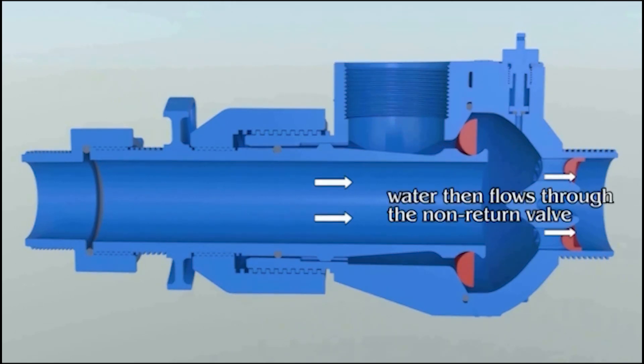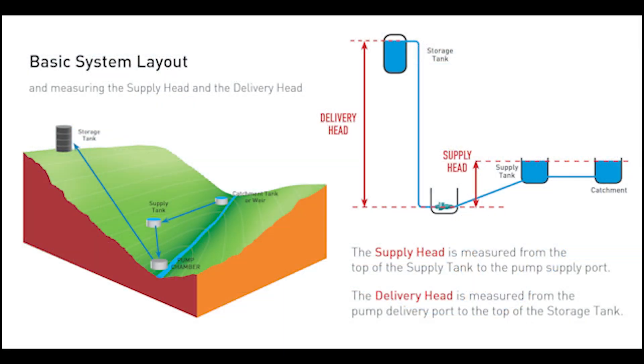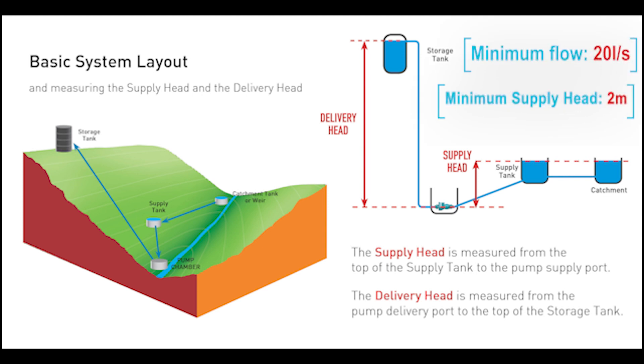The high pressure forces water to exit at a very high pressure through a non-return valve. Our pump's minimum requirements are a 2 metre supply head and a flow rate of 20 litres per second.